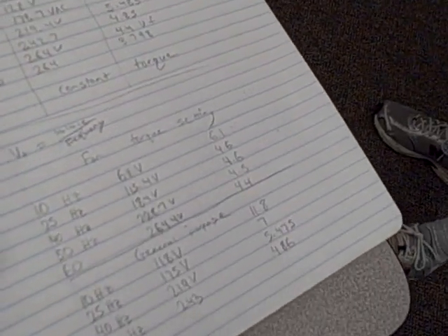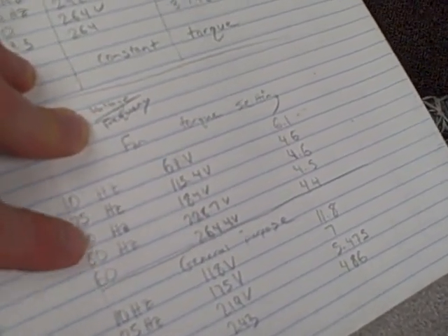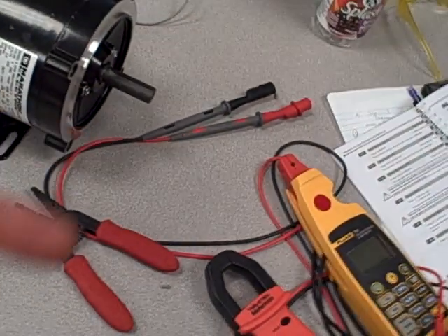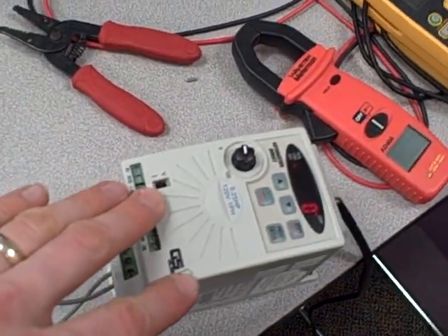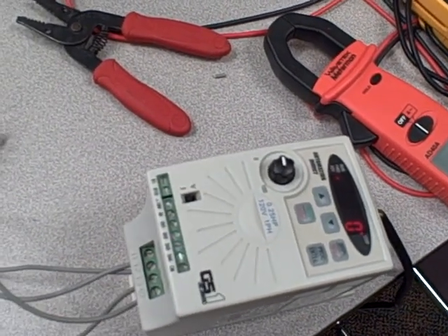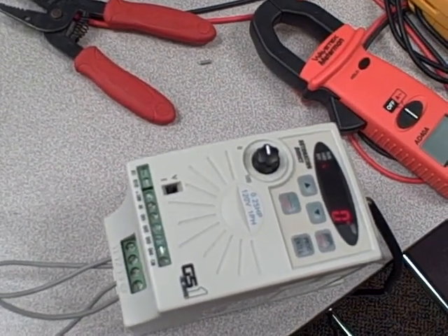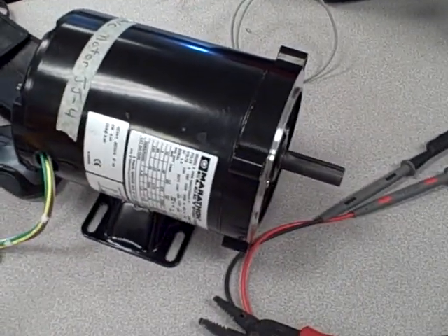Other loads are just the opposite. They require higher torque at the full speed and lower torque at the low speed. For example, turning a fan or a centrifugal pump. As the impeller turns slowly, it doesn't need a lot of torque. And so there's an application where you can program the drive to put out less volts per hertz at the lower end and reduce the amount of current to the motor, and thereby cut down your power consumption, your heating in the motor, and your torque, because you don't need it for those sorts of loads.